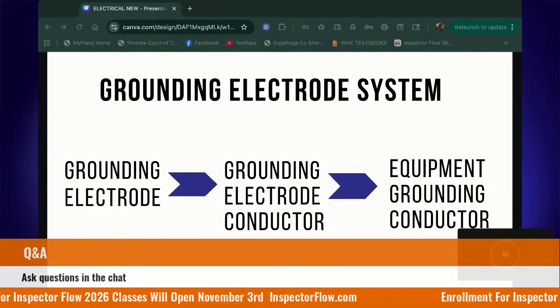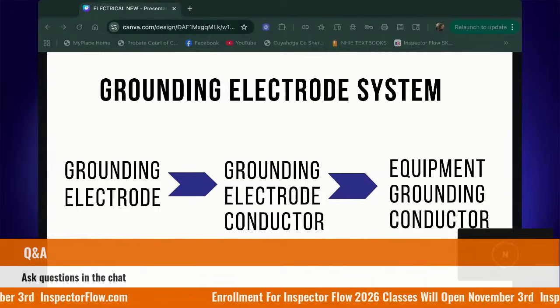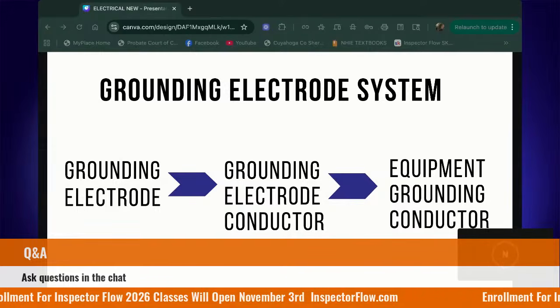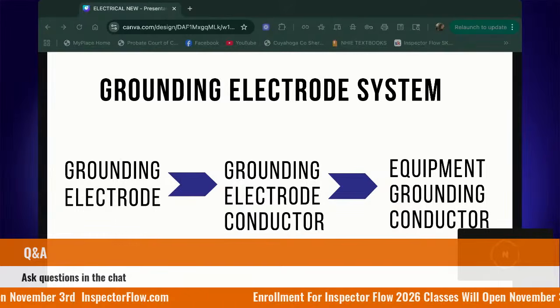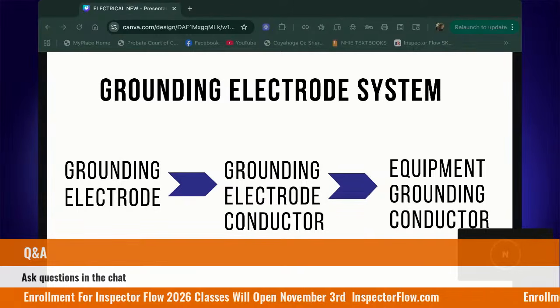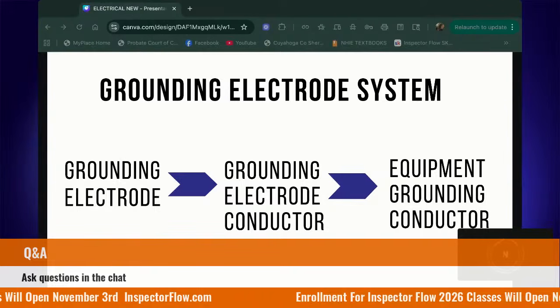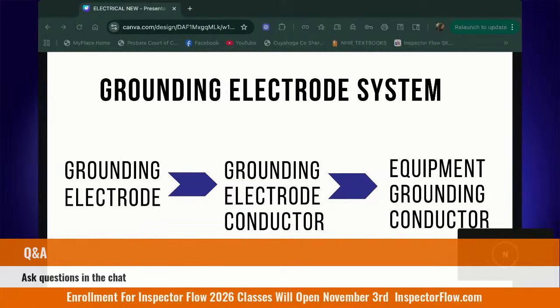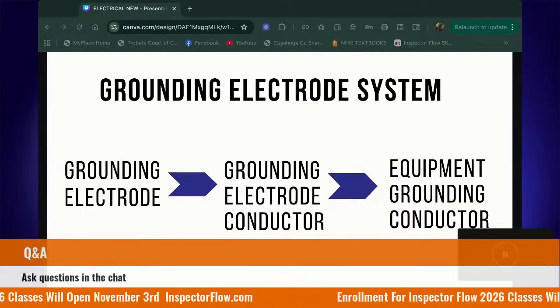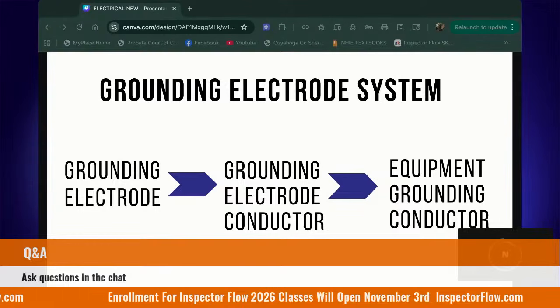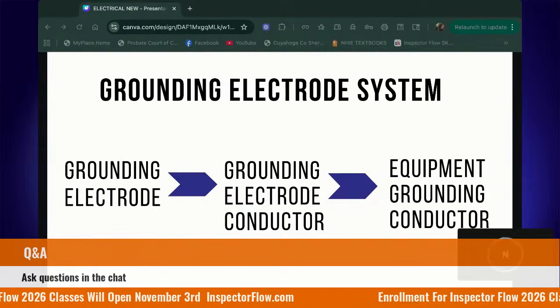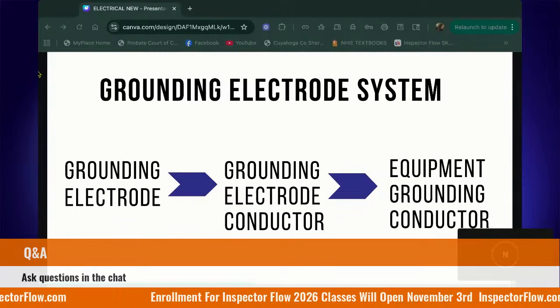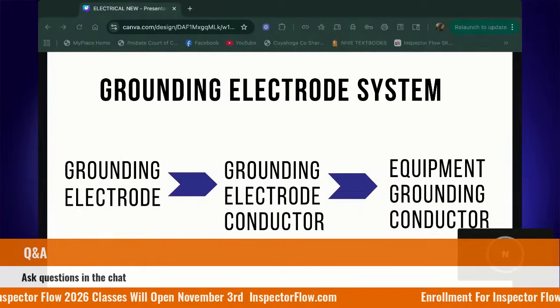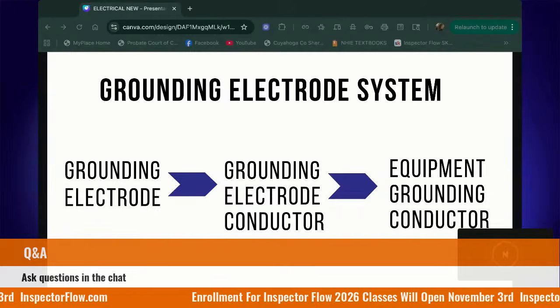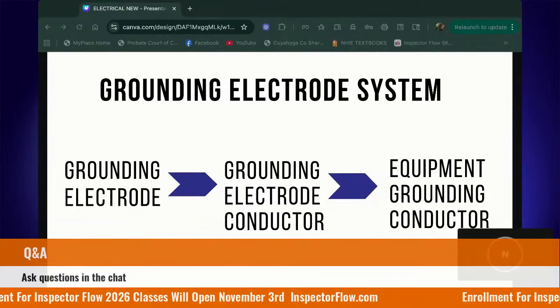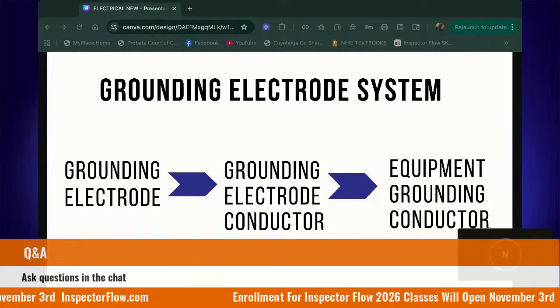It provides connectivity between metal. You were asking a question about the bonding jumper, right? I'm saying it's a conductor, so it's still connectivity between the metal parts. So what does it connect between in the main panel? The bonding jumper is connecting what? The neutral and the ground. So if the bonding jumper is connecting the neutral and the ground, wouldn't I be able to have neutrals and grounds terminating on the same bus bar because they are bonded together? Yes. Oh, okay. Great. Thanks.